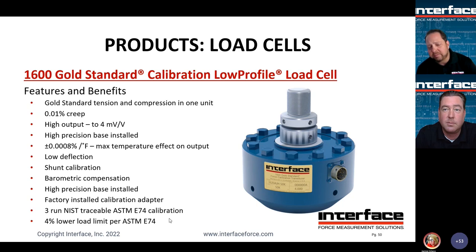Repeatability, if you have nonlinearity in a standard, but you know exactly what it is and it repeats to that every single time, then the overall error there for that load point is going to be known and very small, right? So cal adapters, why are they important? Why do they exist in standards? Because again, we're taking some of that uncertainty and we're reducing that error budget, if you want to look at it as a total system, by ensuring that you're going to get much more consistent load cell performance by having the thread engagement a little further away and having the threads internal to the hub all locked in and loaded at a higher than capacity range.